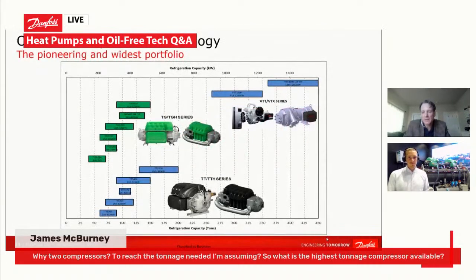I'm going to switch presentations for that. From a capacity standpoint, it's a really good question because it also leads to one of the primary benefits of the technology. From an individual compressor standpoint, and this ties back to the lift optimizations, these are the portfolio of products that we have today. The compressors in blue down below are the TTS and TTH series, which generally fit into about 200 to 700 kW. With Turbocor, the number that follows the name of the compressor is the nominal kW cooling capacity of that design. So a TTS 700 is about 700 kW max design cooling capacity.